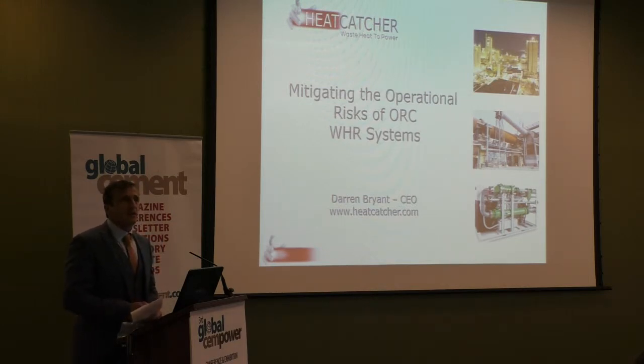We heard yesterday a lot about the larger systems, waste heat recovery, both steam and ORC, very impressive large systems that we saw. The challenge is that most of these are going on to kilns that are more than 3,000 tonnes per day. The majority of the European market is quite small and really quite well thermally optimised. So what you're left with is waste heat which is at low grade, typically below 300 degrees C. So the challenge really is trying to find or come up with solutions for these installations where you can hit the sweet spot with the internal rate of return of greater than 14% to give you the paybacks that you need to make these projects go.